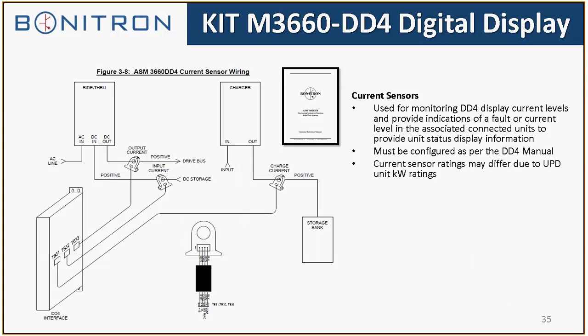This shows a little bit better drawing where the current sensors go, and used for monitoring the current levels, provide indications of a fault, and as I said, they're configured as per the DD4 manual. We make sure you have the current sensors vary with the different ride-through current ratings. So the current sensors are matched up to the actual ride-through that's been specified.